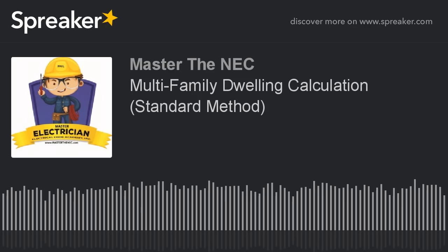Now, let's add all these up at this point. So now you should have two columns. You should have a column for service, and you should have 47,700 for the general lighting and general receptacle applications. You should have 60,750 for the water heaters, for 18 of them, units. You should have 36,000 for the dryer under the service column. You should have 33,000 for the ranges. You should have 81,000 for the heat. Remember, we omitted the air conditioning.